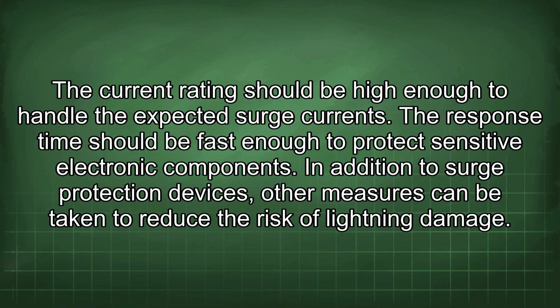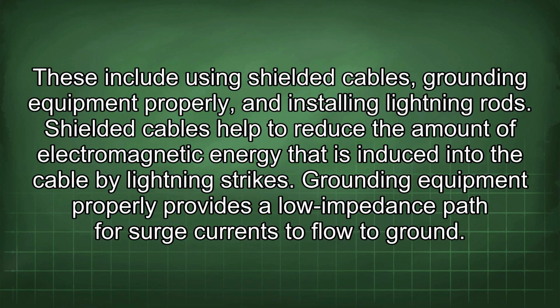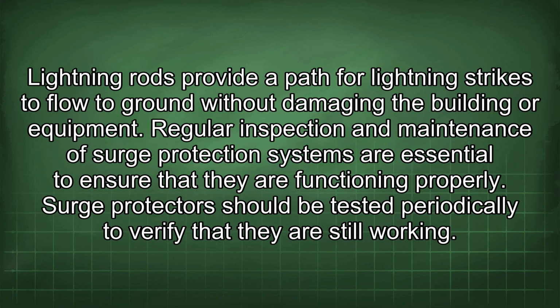In addition to surge protection devices, other measures can be taken to reduce the risk of lightning damage. These include using shielded cables, grounding equipment properly, and installing lightning rods. Shielded cables help to reduce the amount of electromagnetic energy that is induced into the cable by lightning strikes. Grounding equipment properly provides a low impedance path for surge currents to flow to ground. Lightning rods provide a path for lightning strikes to flow to ground without damaging the building or equipment.